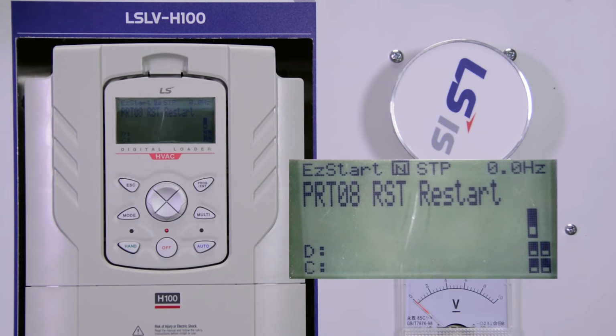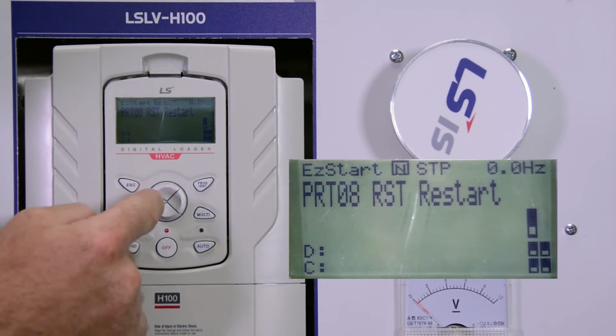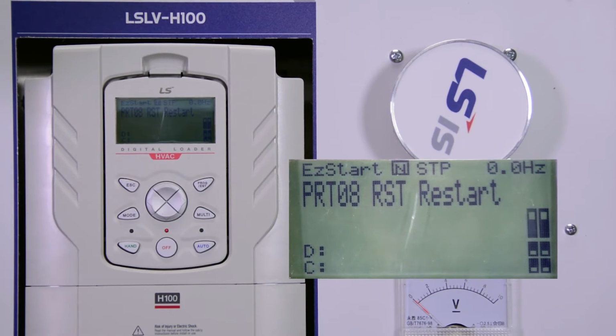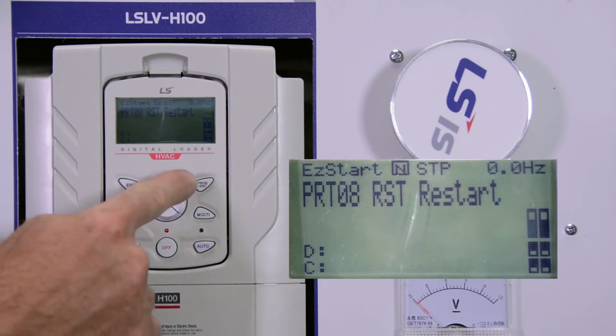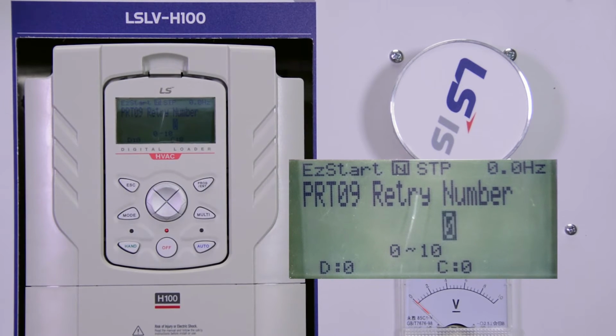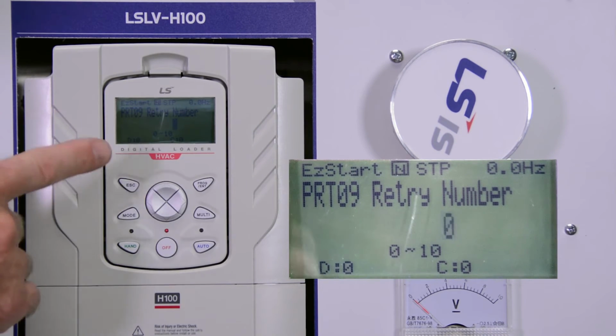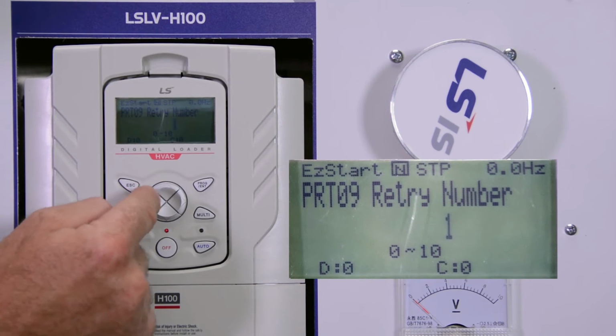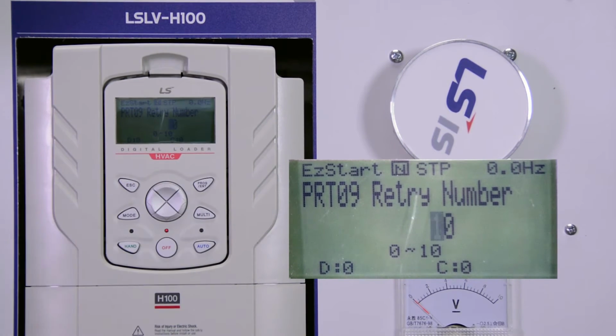The next question wants to know if you want to do an automatic restart. So if you turn the bits both to the on position, select enter, then you set automatic restart. If you want the drive to automatically retry a number of times after there's a fault, you change the next one to whatever number of times you want it to attempt to reset. The max value is 10.